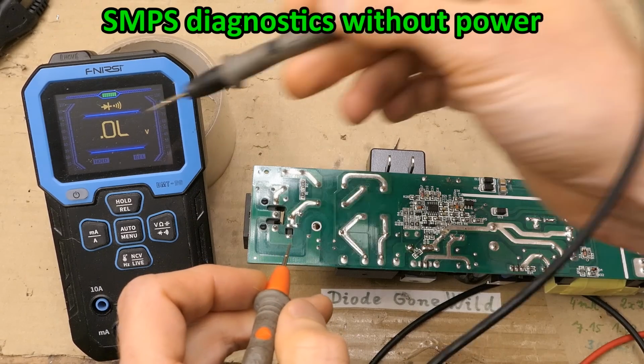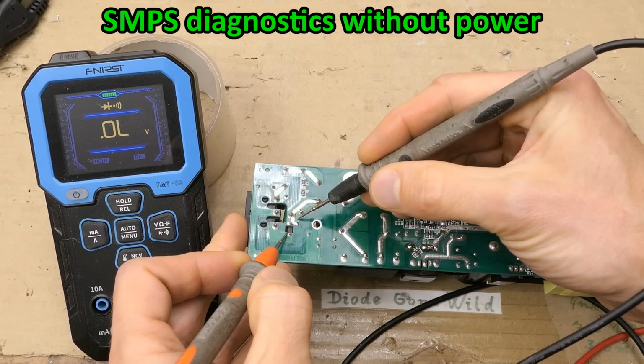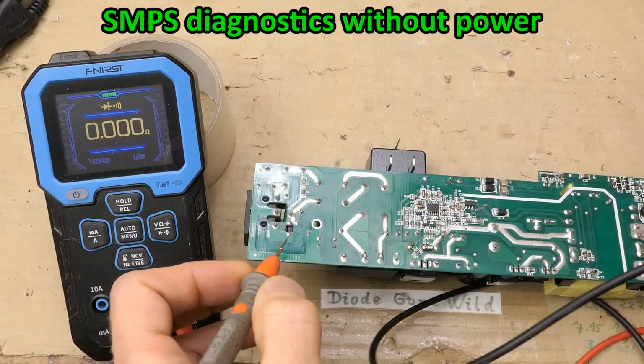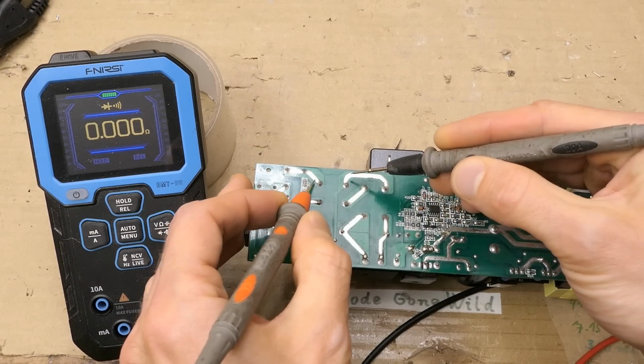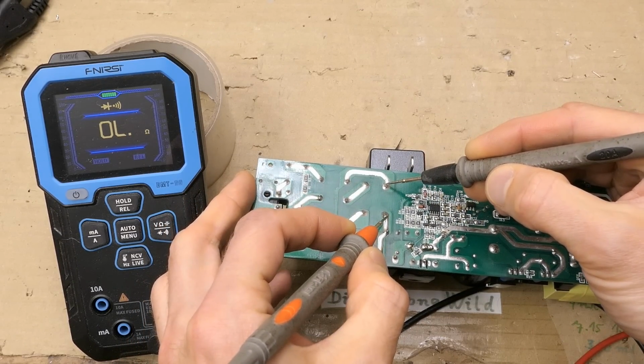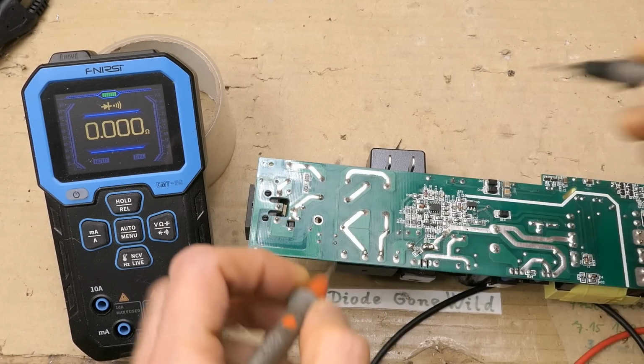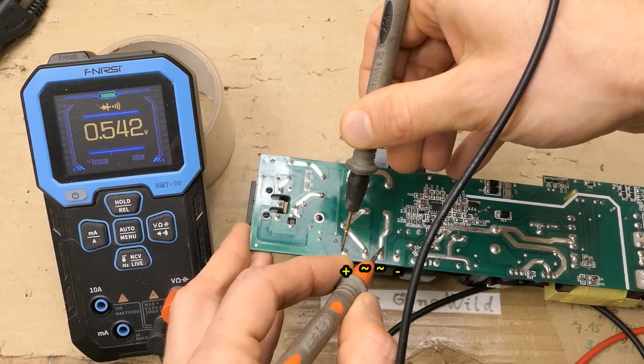Then the measurements. Using a continuity test, you can test the fuse. It's not blown. The interference suppression filters are not an open circuit. A diode test can test the bridge rectifier.